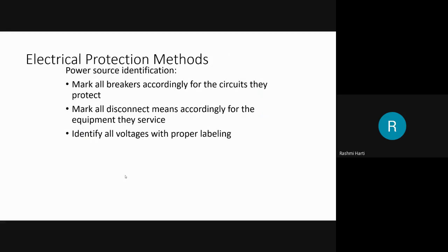Apart from that, you have power source identification. You have to identify the source of power. Okay, so here basically, power source identification. Make sure that all breakers are marked accordingly with the circuits they protect. Make sure that all disconnect means are marked according to the equipment they service. Make sure all voltages are identified with proper labeling. That is very important.